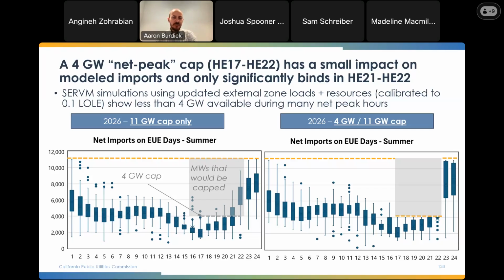On the left, we have the simulation within SERVM of the CAISO without the 4 gigawatt cap, so we just have that yellow line at 11.7 gigawatts. What you see is in the hours where we apply the cap, hours 17 to 22, there actually aren't that many imports, even less than 4 gigawatts, even when we don't constrain it. That tends to rise a little bit later in the evening as the fleet runs out of some of the stored energy on those days with expected unserved energy.